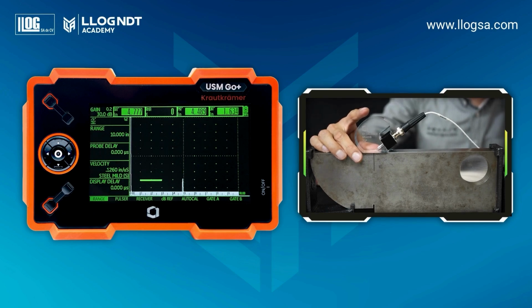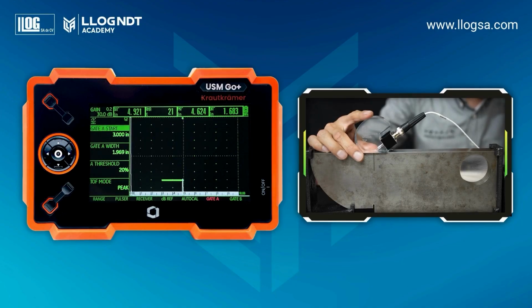We begin by verifying the beam exit index point. Place the transducer on the block, aligning the line marked on the side of the wedge with the center of the 4-inch radius, directed toward the curved surface. Move the gate over the indication and adjust the gain so that the signal reaches approximately 50% of the vertical scale on the screen. Next, move the transducer back and forth until you obtain the maximum amplitude of the indication.